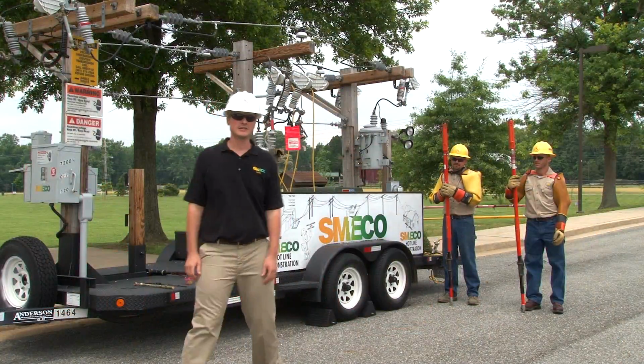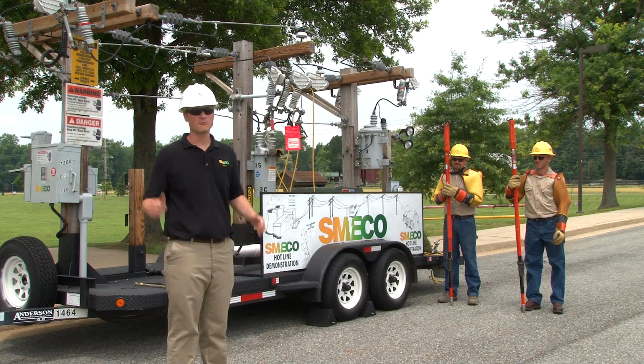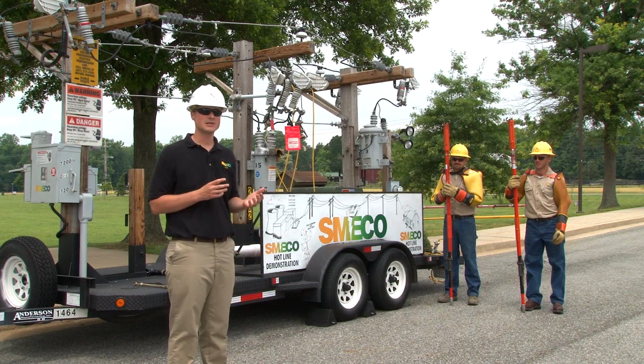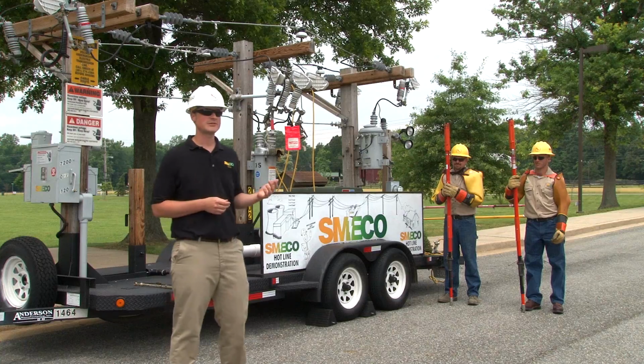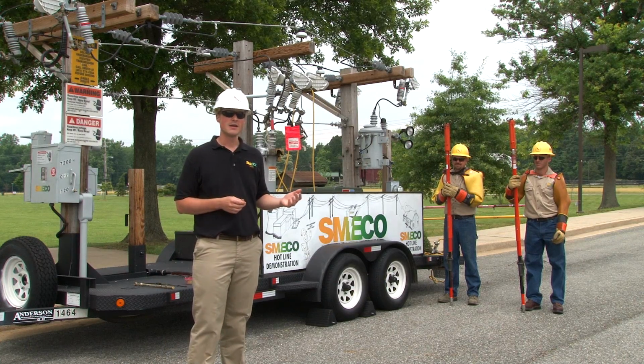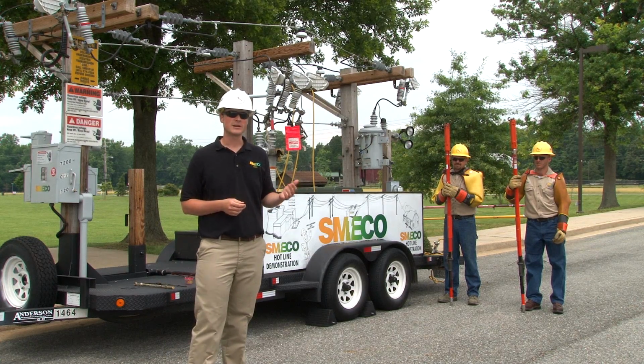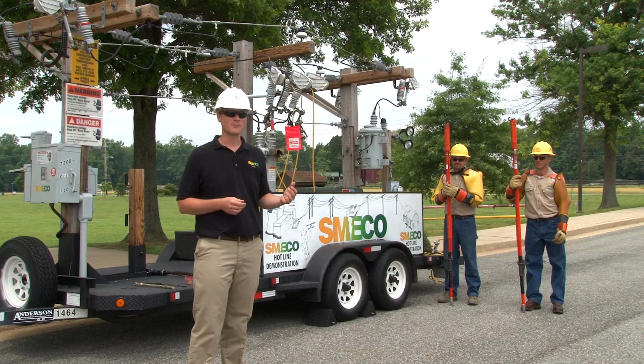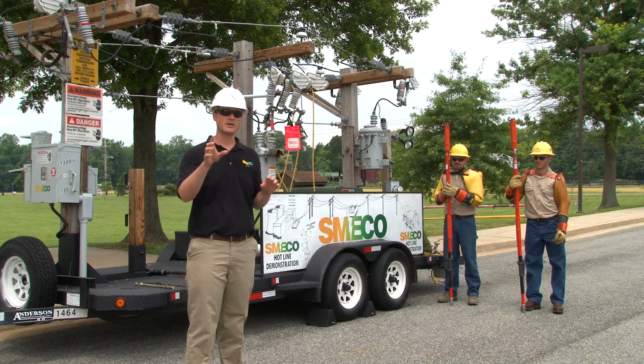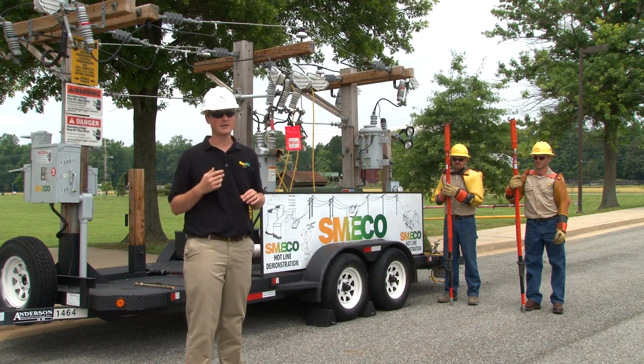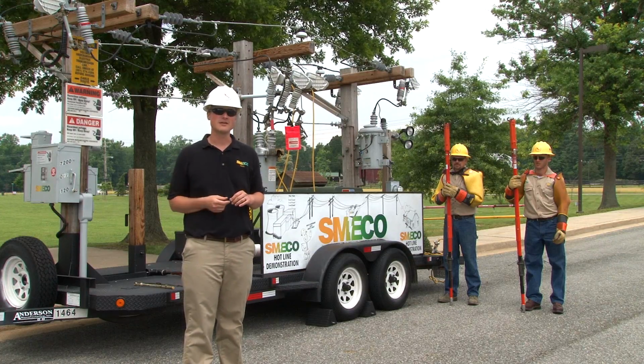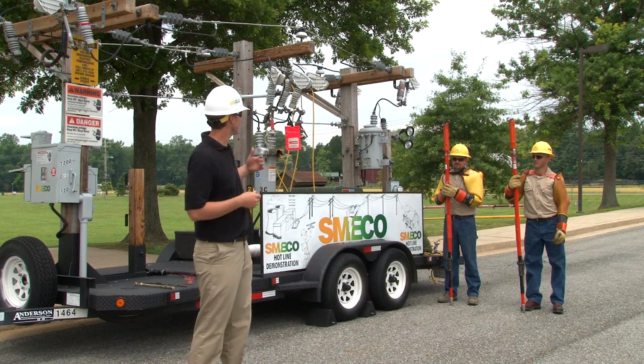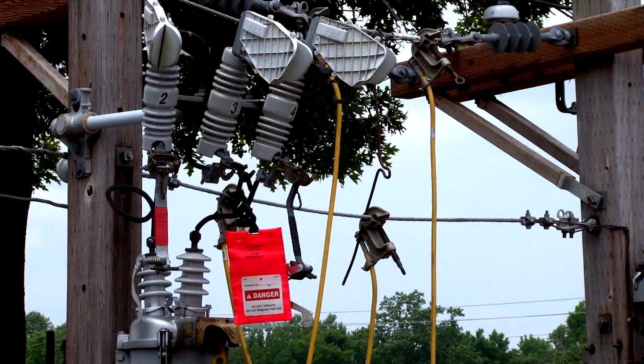All right, Jeremy and Doug installed protective grounds on both sides. One in case that line gets re-energized from the source end, but also for generators in case it gets backfed. Backfeed typically happens when somebody hooks up a generator at their house improperly. It can go through their meter, up through the transformer, and backfeed on our lines at the same primary 7,200 volts. So it's very important our guys put the grounds on both sides.